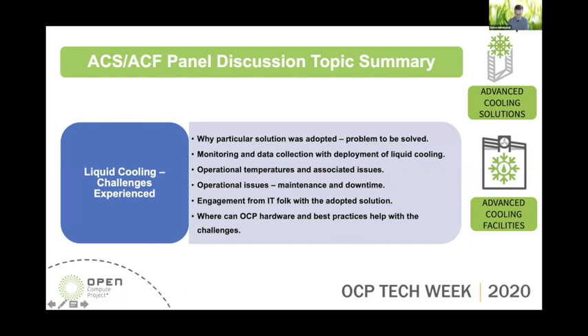Yeah, so there are a couple of things. We've always deployed systems that use negative pressure. All of the liquids used for cooling that came in contact with the chips were drawn under negative pressure, so leaks took the form of sucking air into the plumbing rather than spraying valuable electronic components with water. I think it's easier to detect leaks in this sort of arrangement. You can do this with small groups of racks or at the row level. It doesn't have to be at a facility level, but you can detect a leak and localize it because of vacuum pump activity.